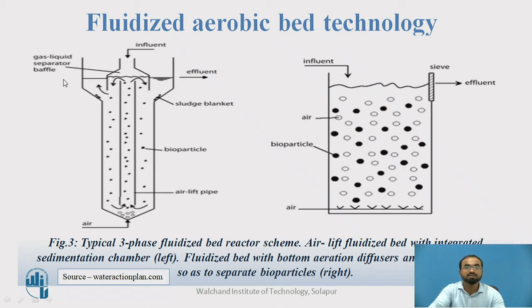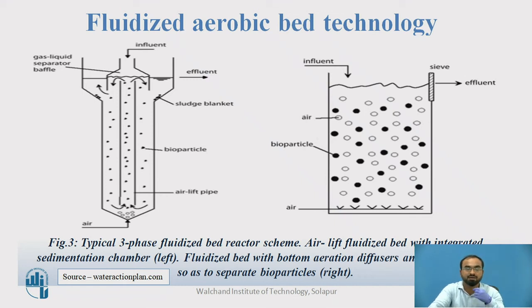A three-phase separator is also provided, separating solids, liquids, and gas. The problem here is that as a lot of air is being provided to keep the bio media in suspension, the air will try to stick into the bioparticles or biomass or media, causing the media to hit each other. The thick biomass formed on the media will separate out and efficiency will go down. Typically, the two-phase system seen earlier gives higher efficiency than this three-phase system, due to this same limitation.